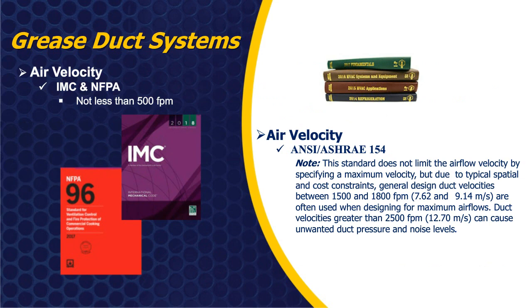All right, I'm going to jump down a little bit to system engineering. Several years ago, the International Mechanical Code and NFPA greatly reduced the minimum velocity when you're sizing a duct system. Currently it states not less than 500 feet per minute. And I'm sure there are several reasons for it. One may be the fact that you see a lot more use of variable speed fans and so forth, trying to minimize the heat loss through the system. But the minimum now in the International Mechanical Code and NFPA is 500 feet per minute.